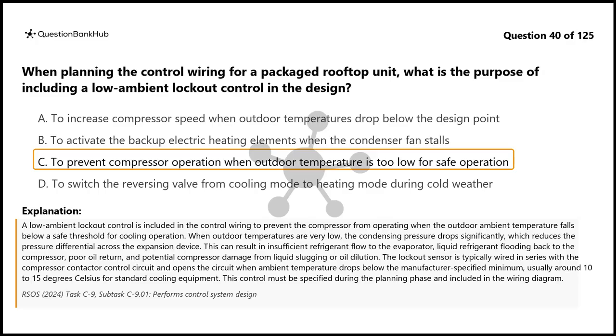When outdoor temperatures are very low, the condensing pressure drops significantly, which reduces the pressure differential across the expansion device. This can result in insufficient refrigerant flow to the evaporator, liquid refrigerant flooding back to the compressor, poor oil return, and potential compressor damage from liquid slugging or oil dilution.